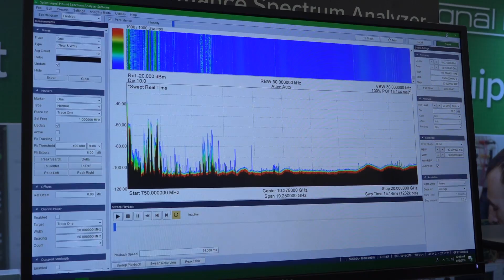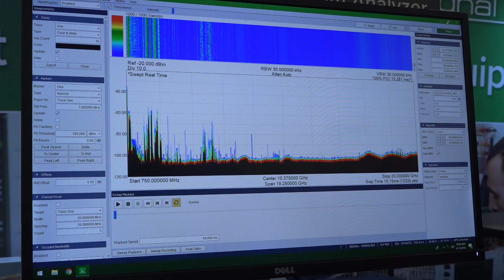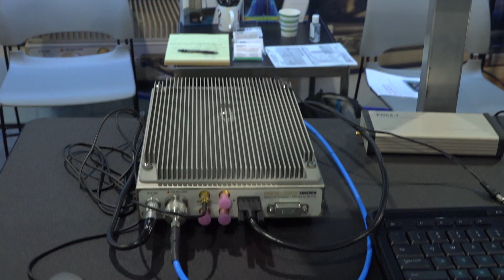There's a full API available. It's a USB-based instrument, connects to the computer. Here, in fact, they just have a little sweep going on here, which I think is worth looking at, just so you can really get an appreciation when I say how fast it really is going on. Right now, it's sweeping from 750 megahertz to 20 gigahertz in 15.14 milliseconds at a 30 kilohertz resolution bandwidth. So it catches extremely rare events very, very quickly. Now, a lot of the processing is done on the unit itself, so the FPGA handles a lot of the required capturing and analysis and alignment.